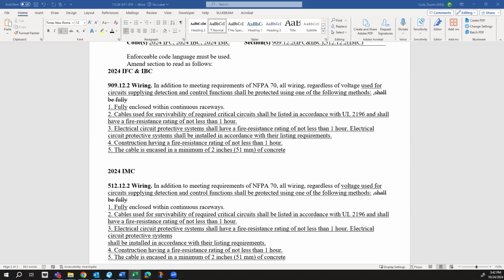This is becoming a big thing with the 501s, because they take the exception for the fifth floor, add pressurization—these are wood frame buildings. You can't install the 2 hour circuits like the Vitalink and stuff, because they're not listed for wood frame buildings—they're listed to be secured to masonry, non-combustible material. That's not a wood frame building. And having to run half-inch raceways through these buildings is very, very expensive.